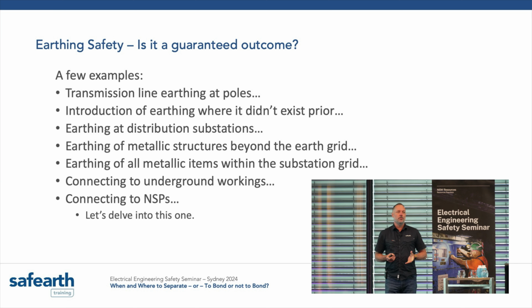If you have, say, a low voltage board on a pole near that system, it will be very much impacted by an earth fault on that line. If there's a lot of earthing at that pole, you'll get a lot more current into that structure, which creates soil voltages that may impact your low voltage board. You can actually control how that works. If you increase the current density by having a smaller, higher impedance earthing system at that one pole, you probably won't change the lightning performance of the line much, but you can absolutely solve the problems at the low voltage board structure.